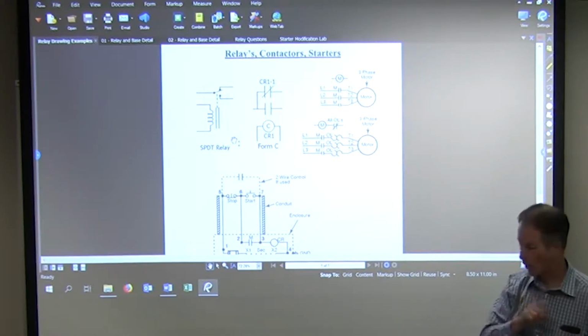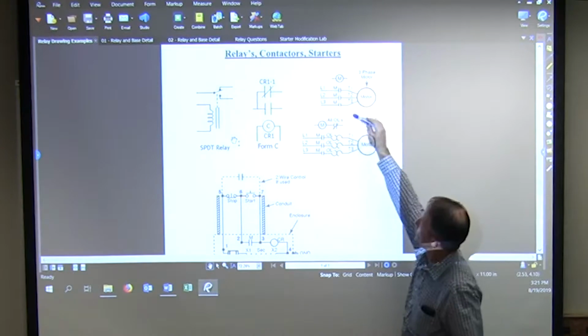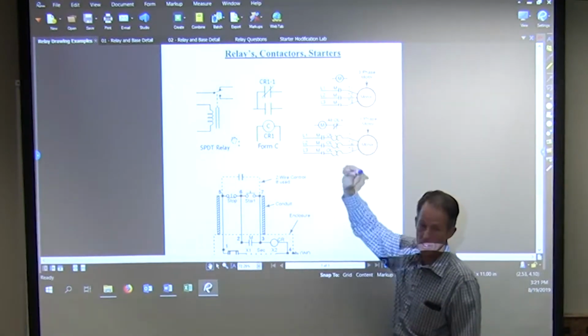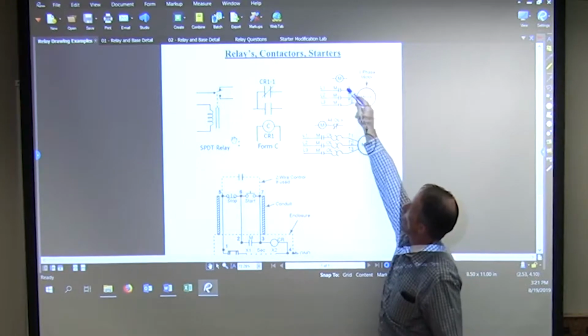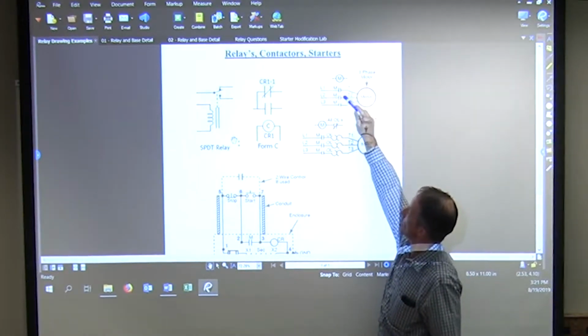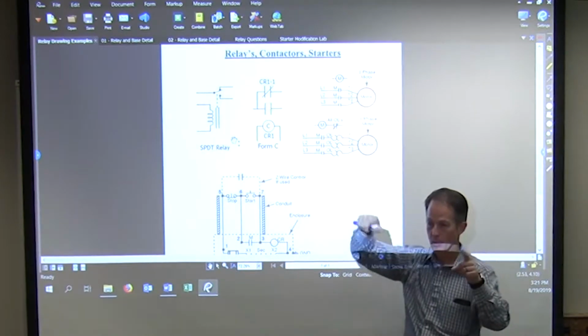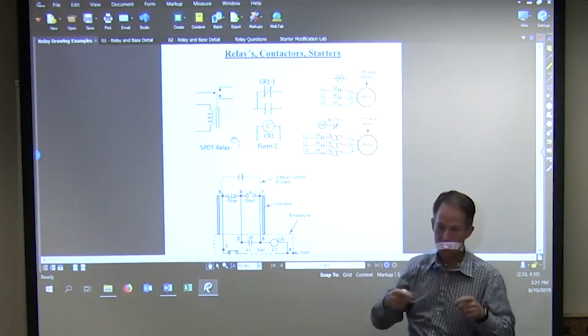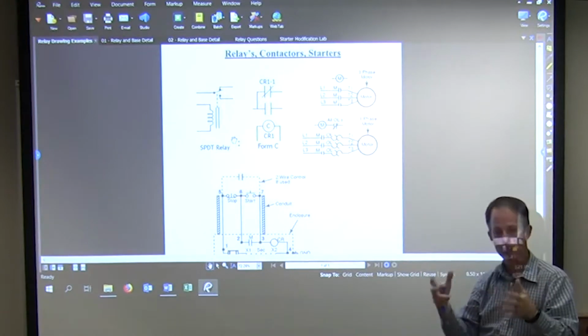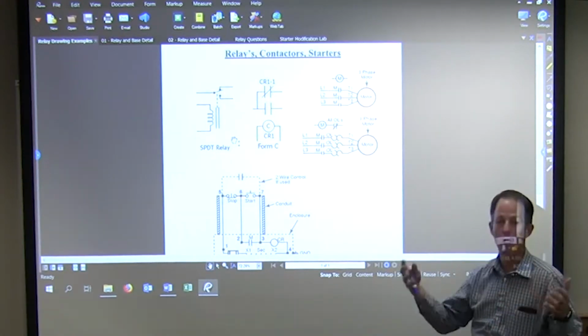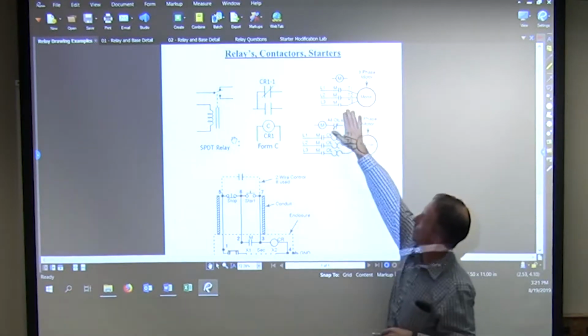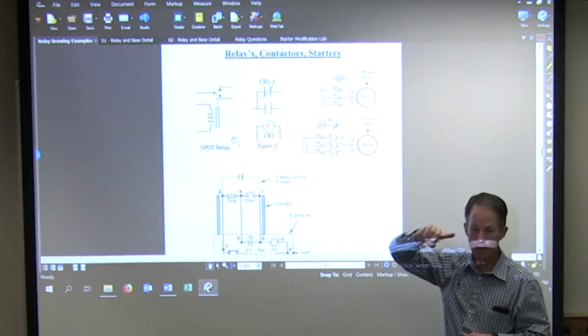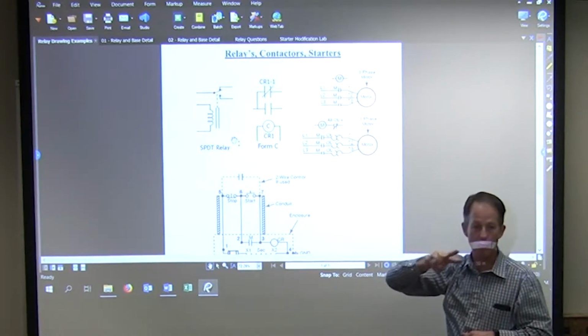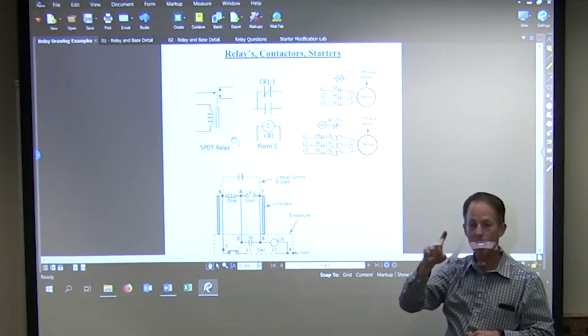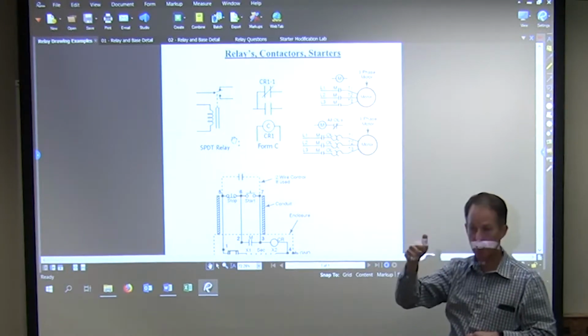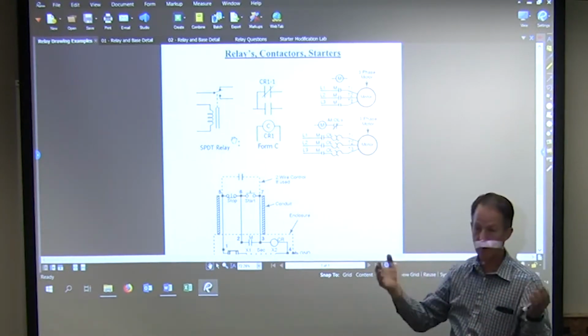Okay. So if, for instance, L3 goes away, the way that I get power through a motor is going from L1 to L3, L1 to L2, L2 to L3, right? It's taking 2 of them, they're wound and then connected. That winding, even though it looks like a dead short because it's an inductive motor, we don't burn it up. They're built to work that way. But if I get rid of one of those 3 legs, I lose actually 2 of the sets of windings. So I only have 1 set of windings working now, so a single phase. The other 2 go away because I don't have a way to finish the path.